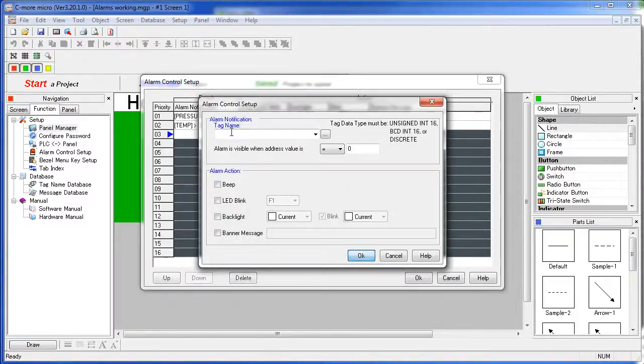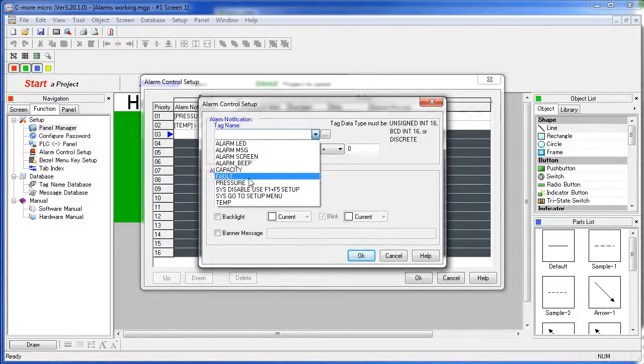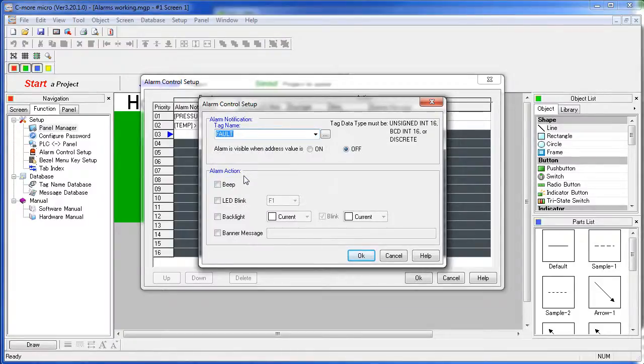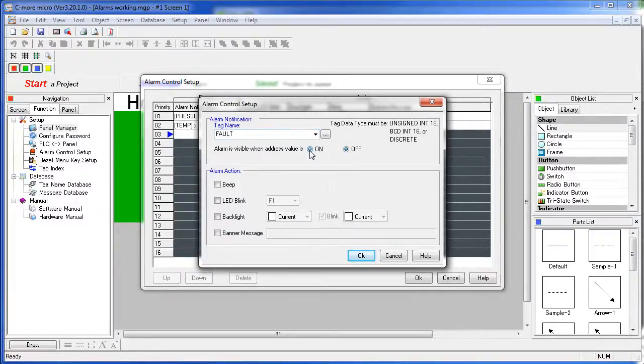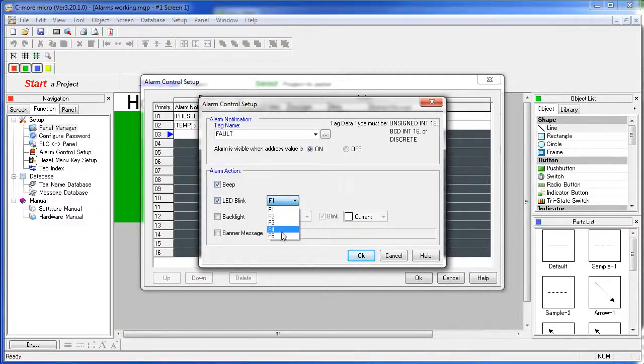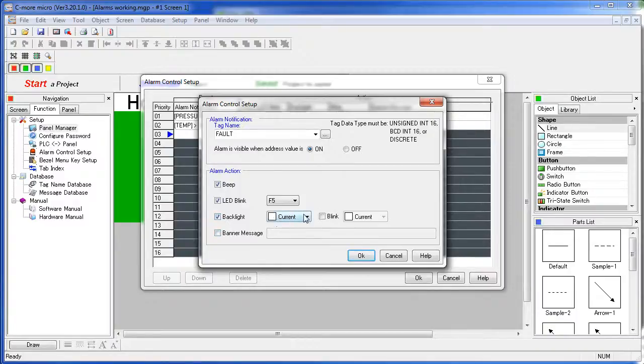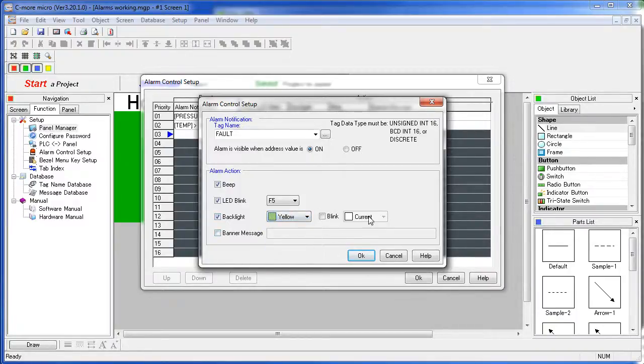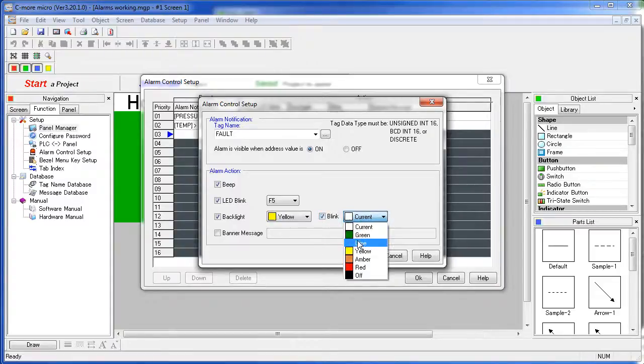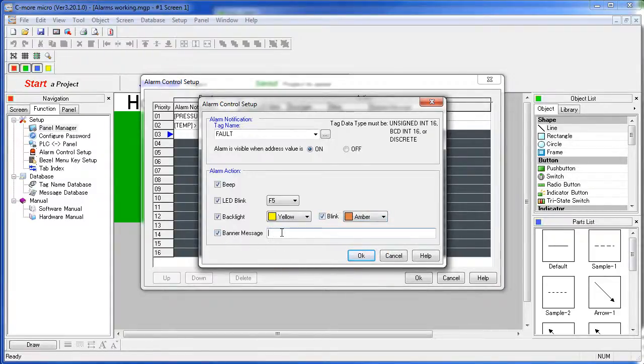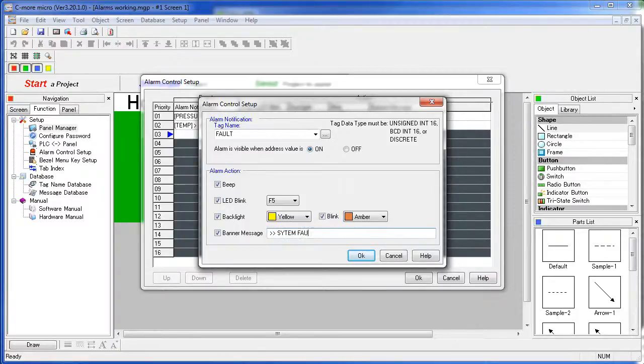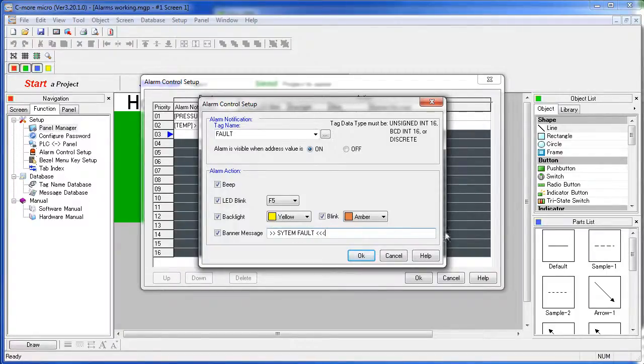And let's do one more. Let's grab this fault tag which is a discrete type. So now we have to tell it it's an alarm when it's in the on or the off state. Let's make this one alarm when it's on. And when that does happen let's do everything. We are going to beep, we are going to blink LED – let's say F5 in this example. We are going to toggle the backlight between yellow and amber and we will put out a banner message across the top of the screen that says system fault.